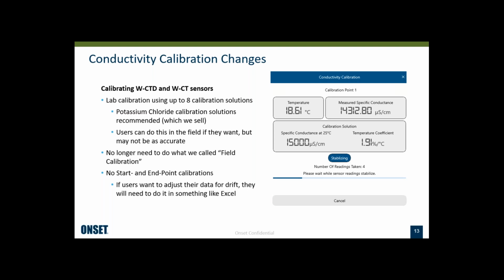But in most cases, we find that our users would prefer to do their own adjustments for drift in the data. It's not always linear, so it's better for them to have control over that if they want. But they'll find in general that the calibration stability of these sensors is better than what we've offered in the past. The biggest issue is, of course, fouling. That will affect the measurements over time. So they do have to clean the sensors depending upon the amount of fouling in their environment.